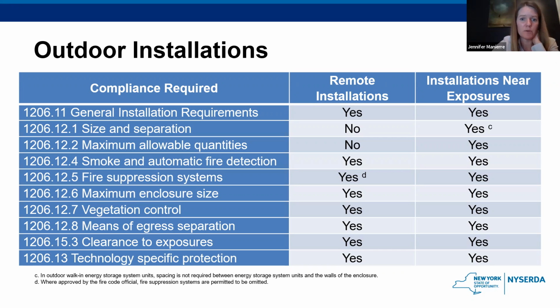And for remote installations, if the fire code official approves it, those installations can forego the fire suppression system. Many may choose not to forego it, but you can if it's remote and not going to hurt anyone if it catches fire. Maybe the system owner would prefer to just let it burn out. But that's a decision the fire code official can make if they want to.